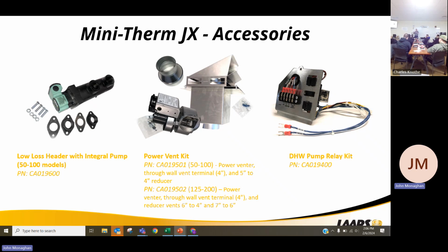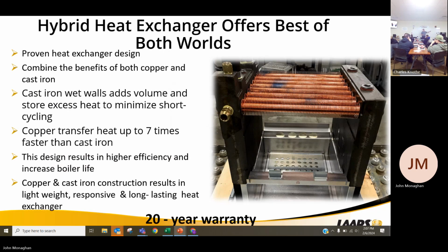We connect it to a system that has 70, 80 gallons of water in it. I have this little bitty heat exchanger that holds maybe, if I'm lucky, 2.5, 3 gallons of water. I send out 180. I heat that water up really quickly. I've got 67 degree water coming back. Cracked heat exchanger, or it's noisy. I say often they sound like sneakers in a dryer until they don't. Once they're quiet again, they're done. Yeah, and once those things get sooted up, not too fun getting them clean again. So we want to not let this condense. I would do as much as we can to keep it from condensing.